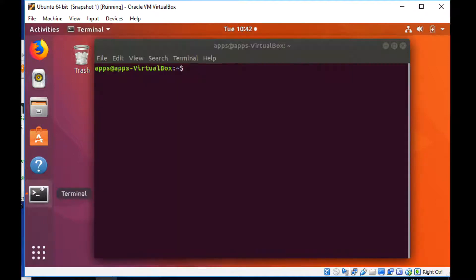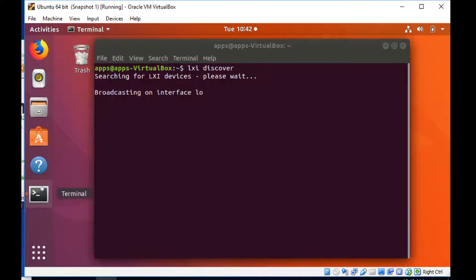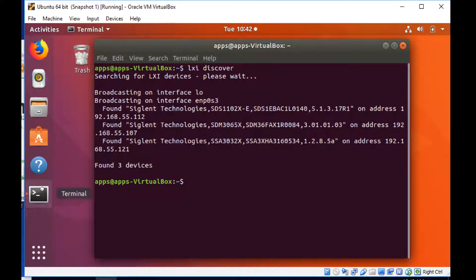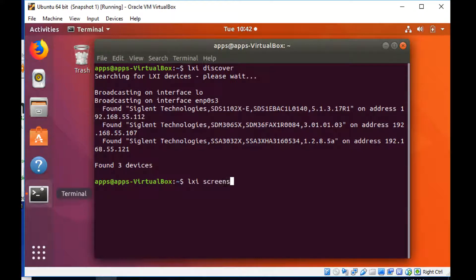So we're just going to fire up a terminal, and I've already loaded the LXI tools. The really cool thing, LXI Discover is going to go out and look at all of the devices that are attached to the LAN. You can see all three of them have returned their IDNs, or their identification strings.